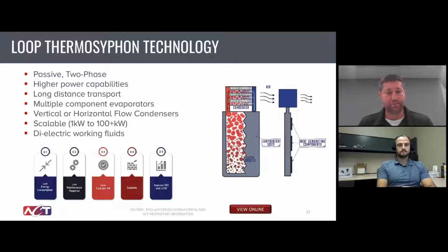So that's kind of the heat pipe side of things. Another passive two-phase solution, kind of a variant off heat pipe technology, is thermosiphons and then loop thermosiphons. So thermosiphon is the name for a gravity-assisted heat pipe. So in those cases, you do not need a wick structure to return the fluid. You're relying on gravity to return the fluid. And in those cases, it can be very similar. A thermosiphon can be very similar to a heat pipe, just unwicked, and knowing that you need to couple your heat sink above your heat source. So if you have that scenario, you can use thermosiphon technology and get the benefit of the gravity assist.